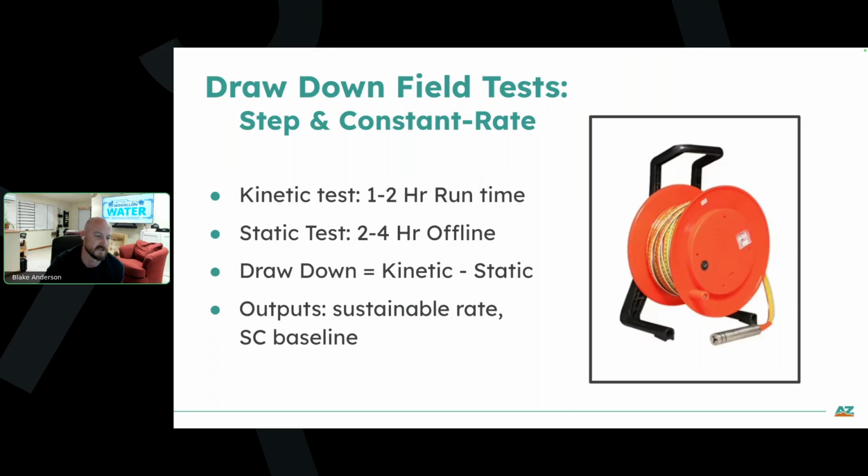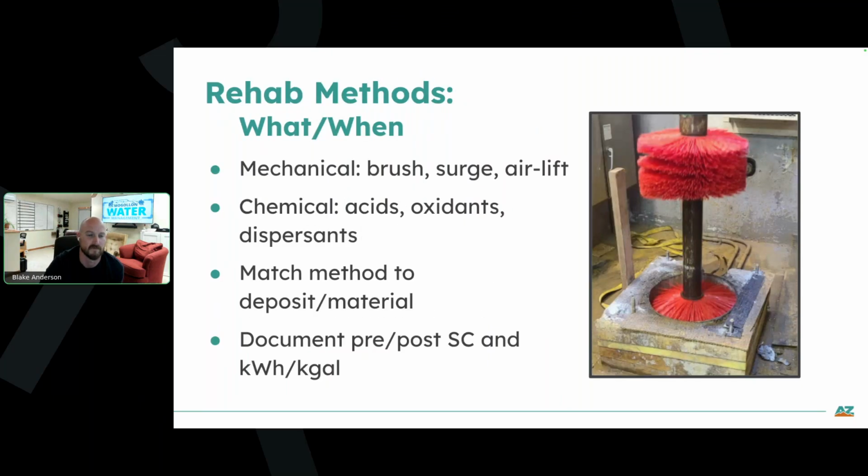But let's say that you're just seeing a decline. It's not necessarily always going to be groundwater decline. It can be a lot of times that your casing's just getting plugged up or fouled. And so when that happens, ideally you're in a situation where you've got the pump pulled, it was a planned pull, and you have a little bit of time to actually get in there and do some inspecting. I always recommend that when we pull a pump or motor, obviously we inspect the pump and motor, but we do a video log downhole just to see what things are looking like.